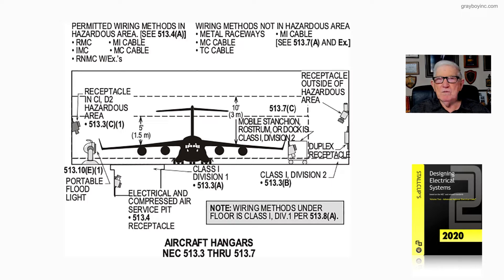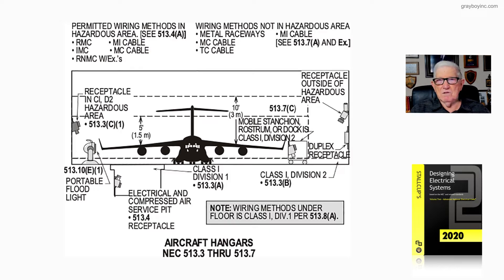In hazardous areas, you have rigid metal conduit, IMC, rigid non-metallic conduit, MI cable, and MC cable. There are some exceptions when using rigid non-metallic conduit, as noted in the illustration.